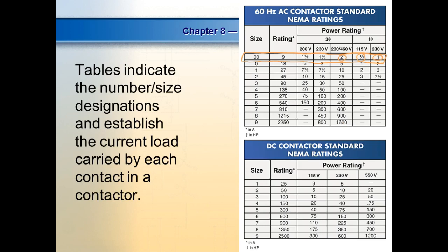DCs, we don't have a 00. So we got a 00, and I think our motor is a motor and a half horsepower. So we're using a double zero contactor, right? Three phase. And we're running ours on 208, so we could run up to 1.5 horsepower motor on that contactor. We're running half horsepower.